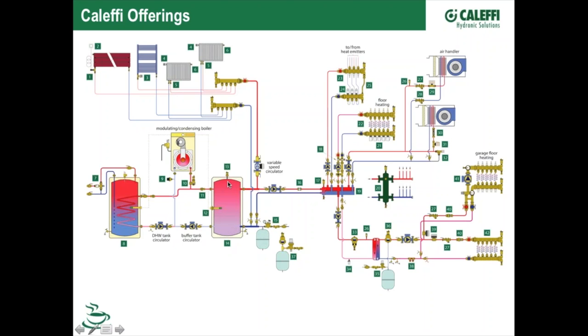So this vessel, being a big wide open space, is a continuation of that point of no pressure change. So this pump here, being that this whole area here, so to speak, is the point of no pressure change, is pumping away from the point of no pressure change, and it's delta P into the boiler here, because that's what we're doing, is pumping right into the boiler here. And the same thing over here. Even though it looks like it is on the red line, it looks like a supply line, we are still pumping away from this point of no pressure change.